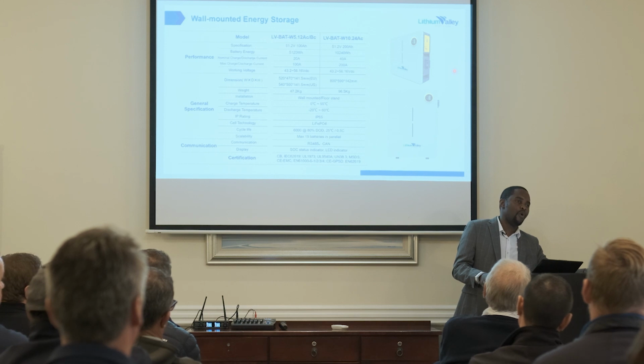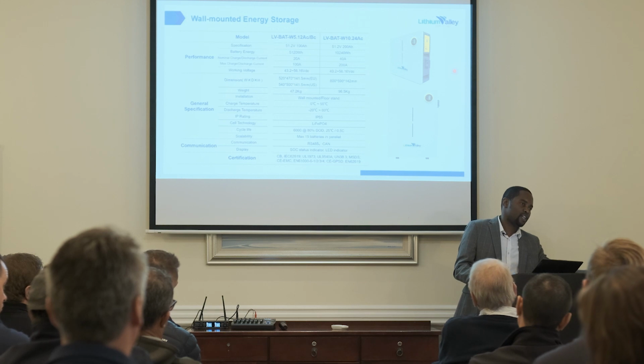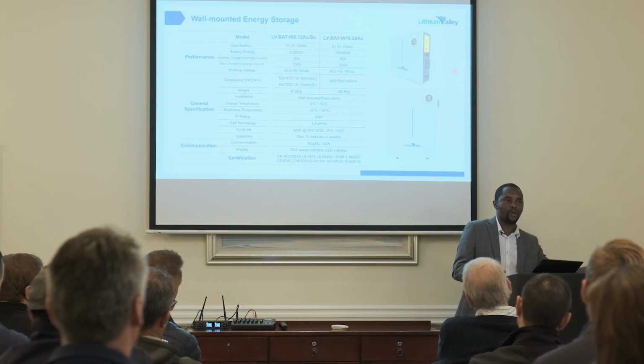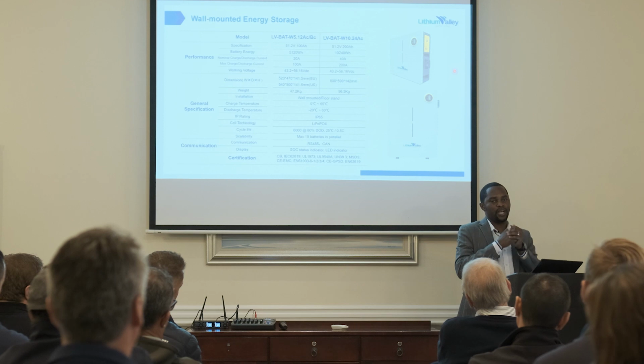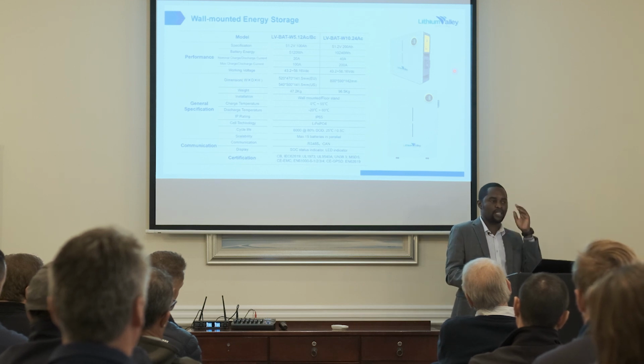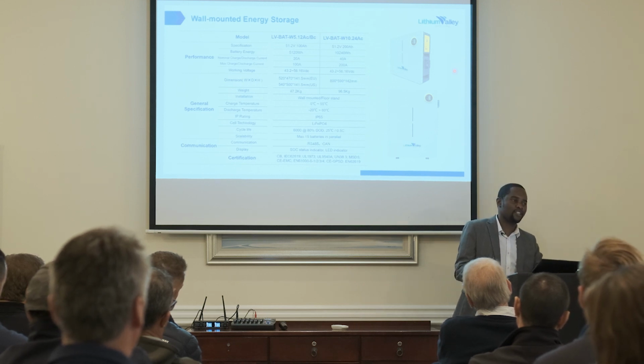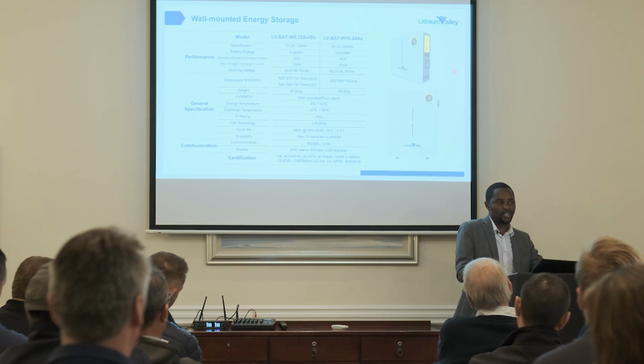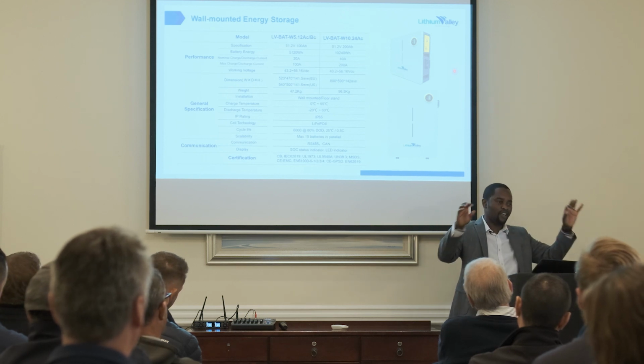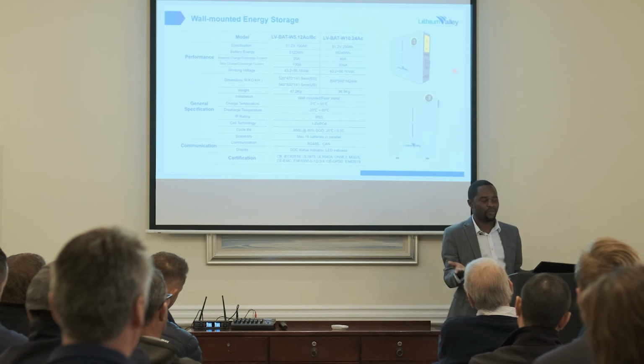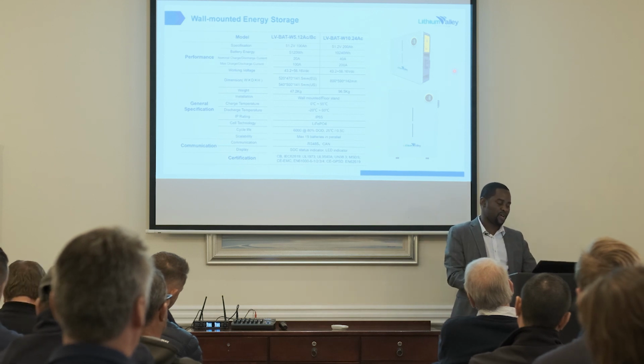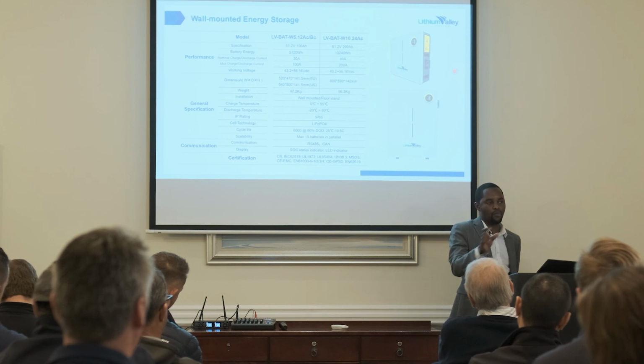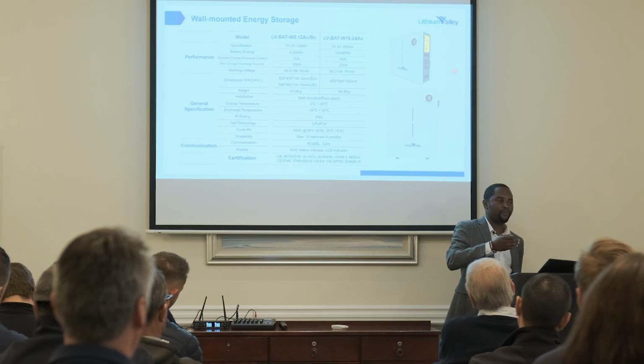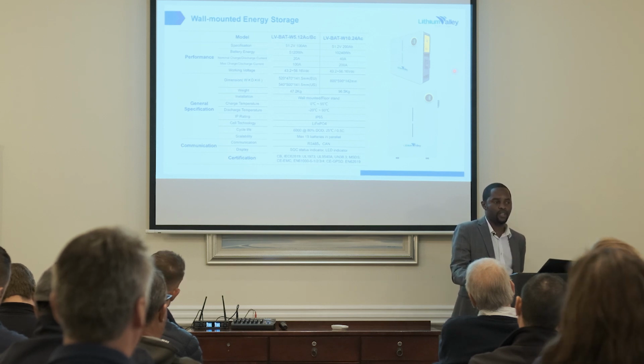So when you've got more in parallel, you now need 10 kilowatt. You can have 10 kilowatt, which is 200 amp in that cable. So you are going to a bus bar. When you say a bus bar, someone is saying, oh, now I need to buy an extra thing. I mean, in bus bar, we're talking of 200 or 300 rand. You just buy a copper bar for the negative and another copper bar for the positive. So if you call it a bus bar, it may sound fancy, but it's just a copper bar, which is very cheap. Then from that copper bar, you are buying an extra thicker cable, 35 square or 50 square for an 8 kilowatt.